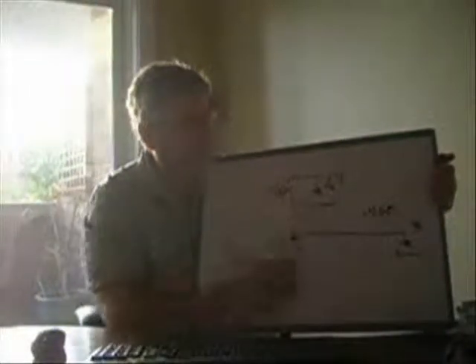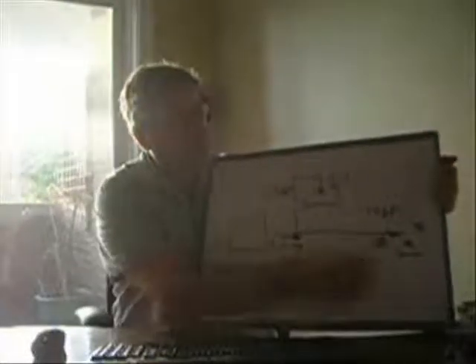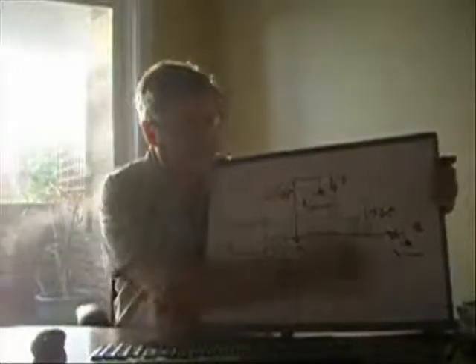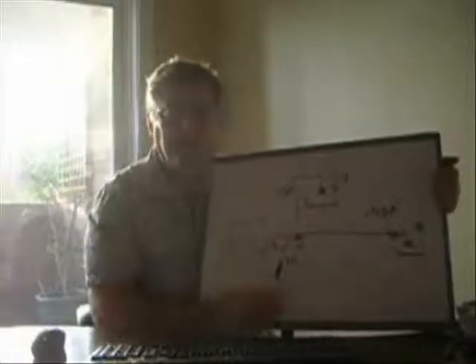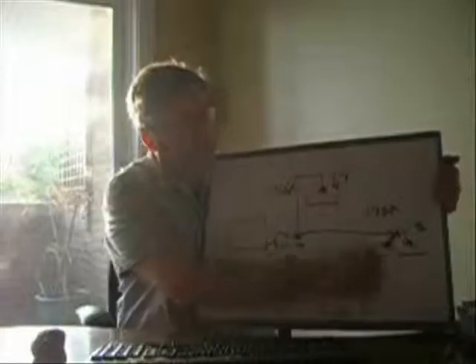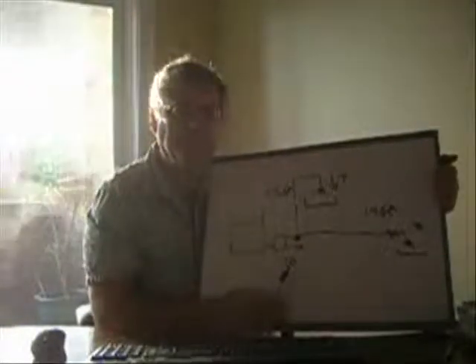So the way to ensure that this is what you're going to get is you're going to put a valve here. This valve is going to control this output. So when you start your system, if you've designed everything properly, when you turn this whole thing on, you're going to adjust this flow rate here so that you're matching your 3 GPM and this should automatically set itself to 7 GPM because that's where you designed it.